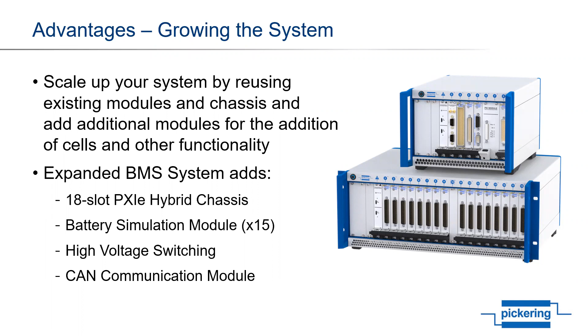We can also still use the 42-924 8-slot PXIe full hybrid chassis for the other modules in the system, along with a CAN communication module for testing BMS communications. Due to the higher voltages now present, we've added a high voltage module, the 40-330 750 volt uncommitted relay module.